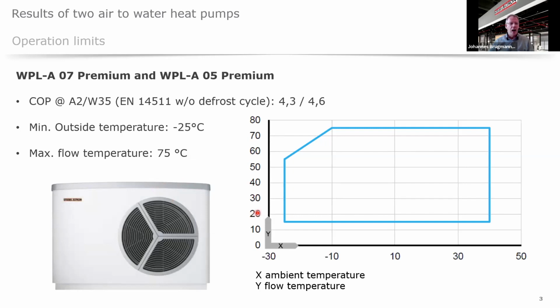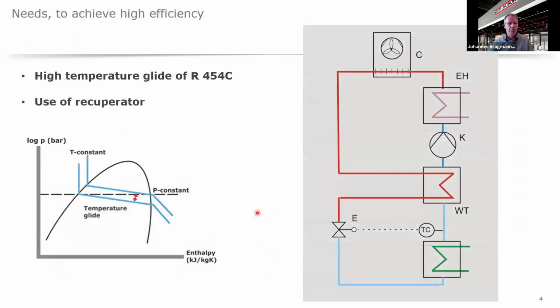But R454C also has some disadvantages. One of these disadvantages is a quite high temperature glide of 6 to 12 Kelvin, depending on where you are in the wet steam area.